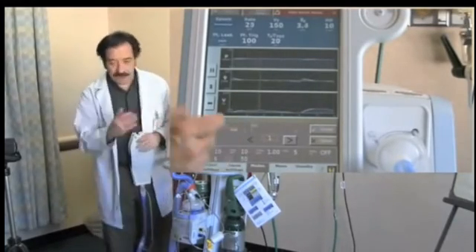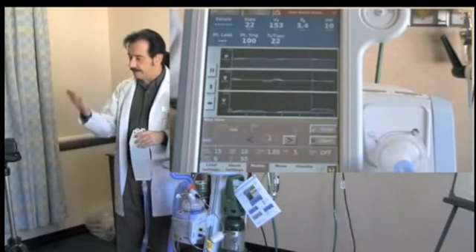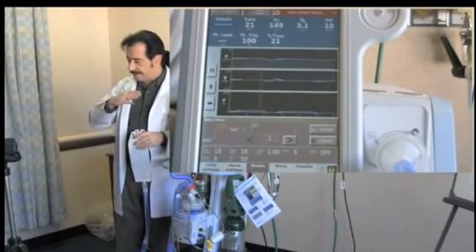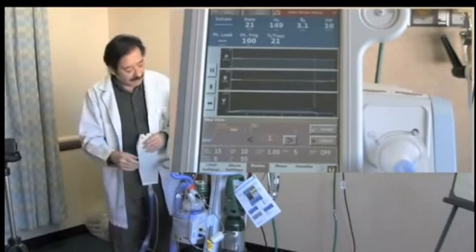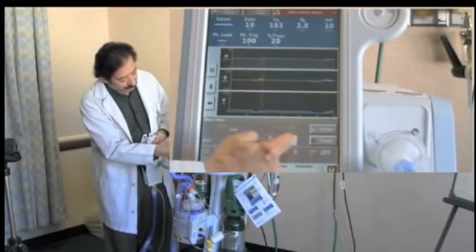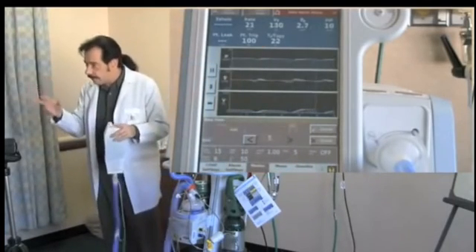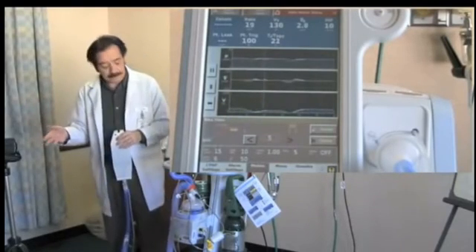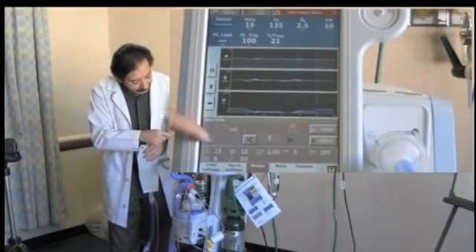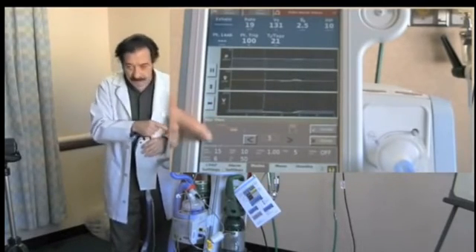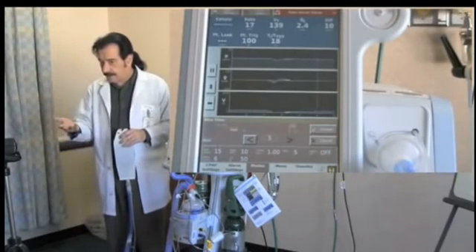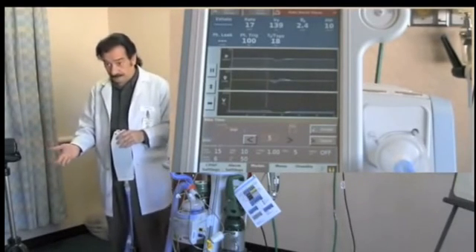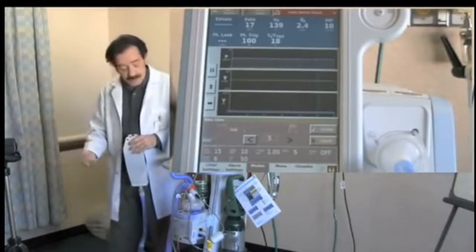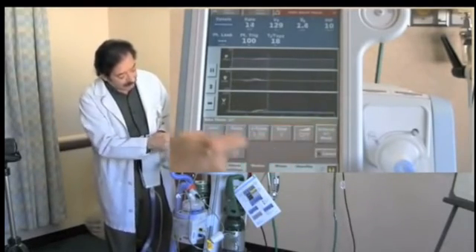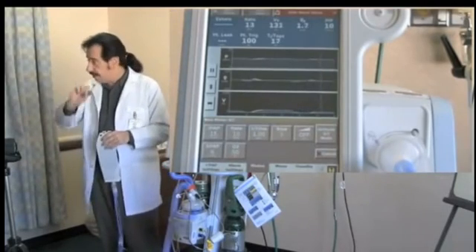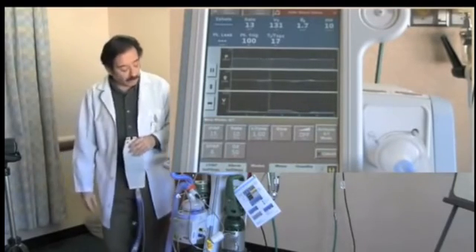So we can reduce the incoming flow or the acceleration of the flow and make that more gentle, kind of slow it down a little bit at the start of inspiration with a setting of 1 through 5. Now 5 gives you the slowest and therefore maybe the most comfortable inspiratory flow rate. But if I accept that, then I've cut off a significant portion of the area under the curve of the pressure waveform, so my volume is going to be lower. Okay? I'm losing volume by providing comfort. So one of the ways to combat that is to increase your I time a little bit to make up for that cut-off edge, okay? And they'll restore their volume.